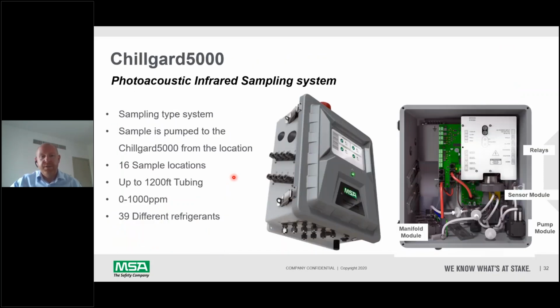So the first method of detection we use is our sampling system. A sampling system contains a pump, and what it does is collect samples from different locations around a plant room through some form of tubing, whether the tubing is polyurethane, copper, or stainless steel for some pharma applications. The tubing is distributed in the plant room, and the pump sucks the samples into the sensor, and then the sensor analyzes the gas to see if there's ammonia or any other type of refrigerant in it. If it detects the gas, we get an alarm on top, or we get signals out to alert the facilities manager that there's a gas leak at that particular location. For the Chillgard5000, the Freon model has 39 different gases on it, and we can add new gases to it. The important thing to notice here is that there's only one sensor. We only need one sensor in this model.